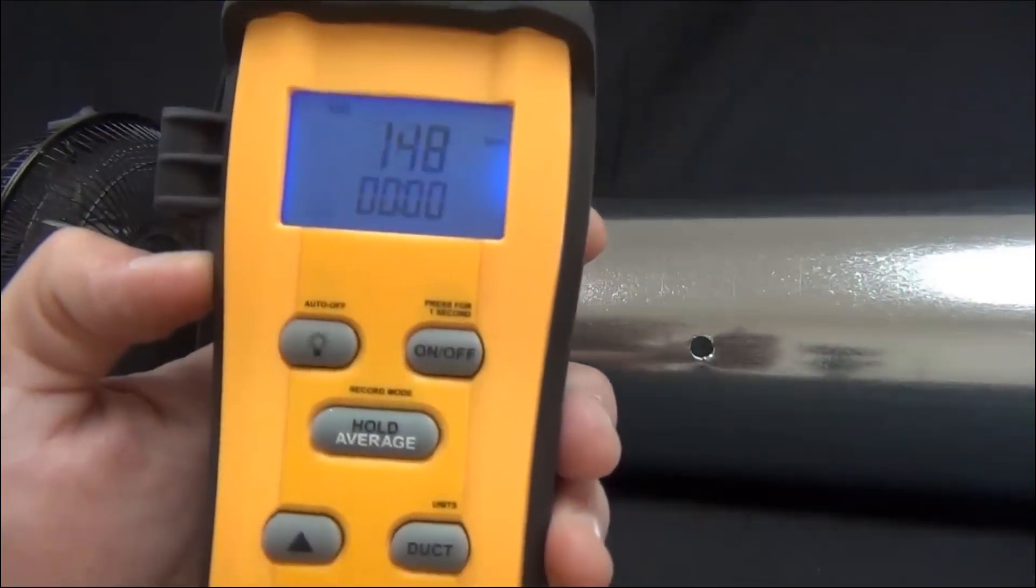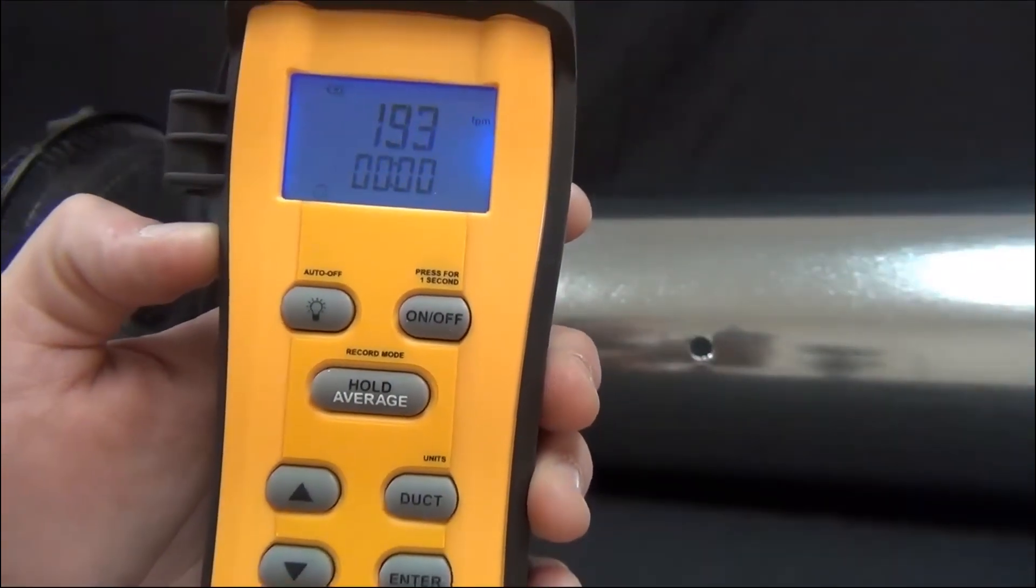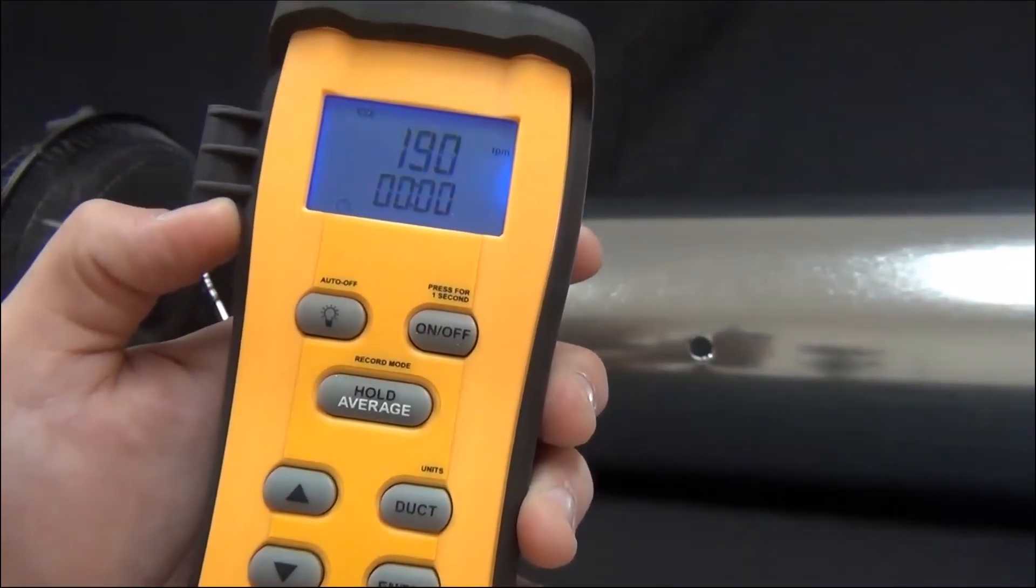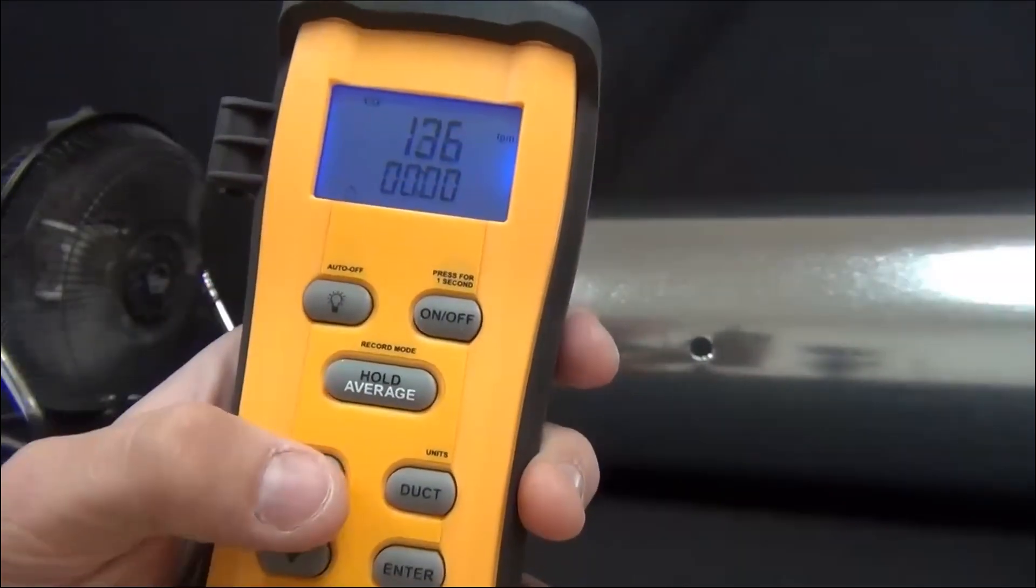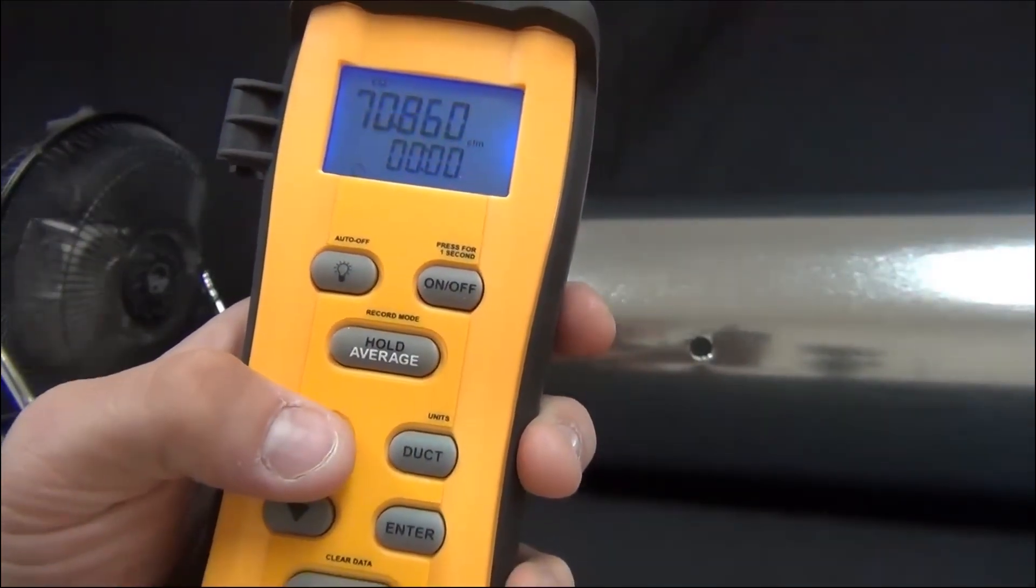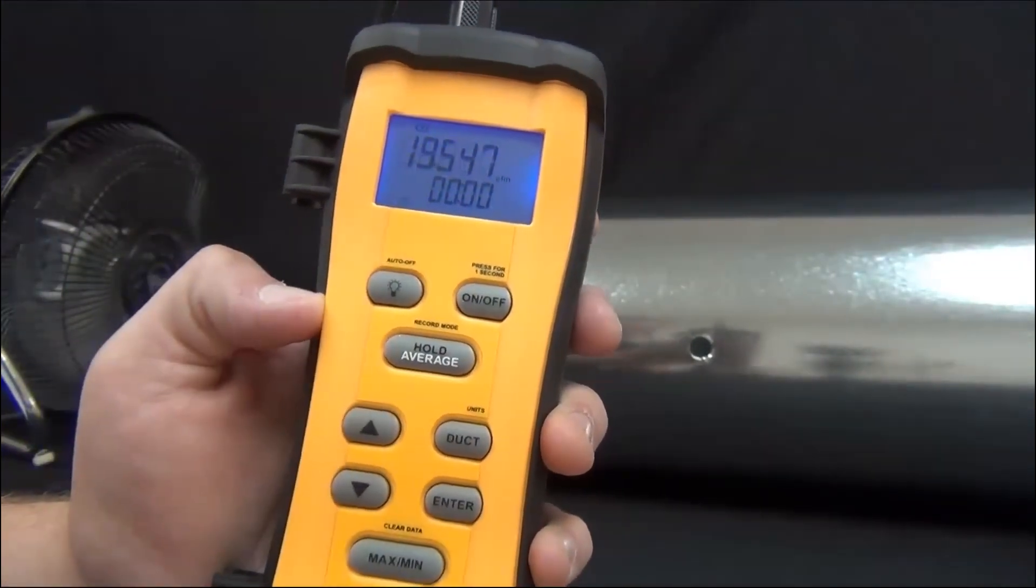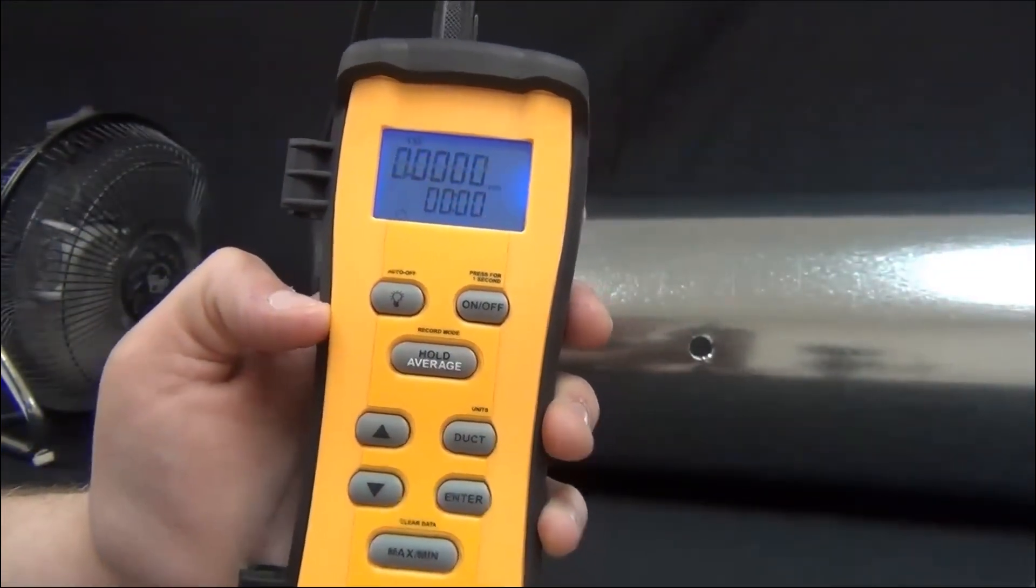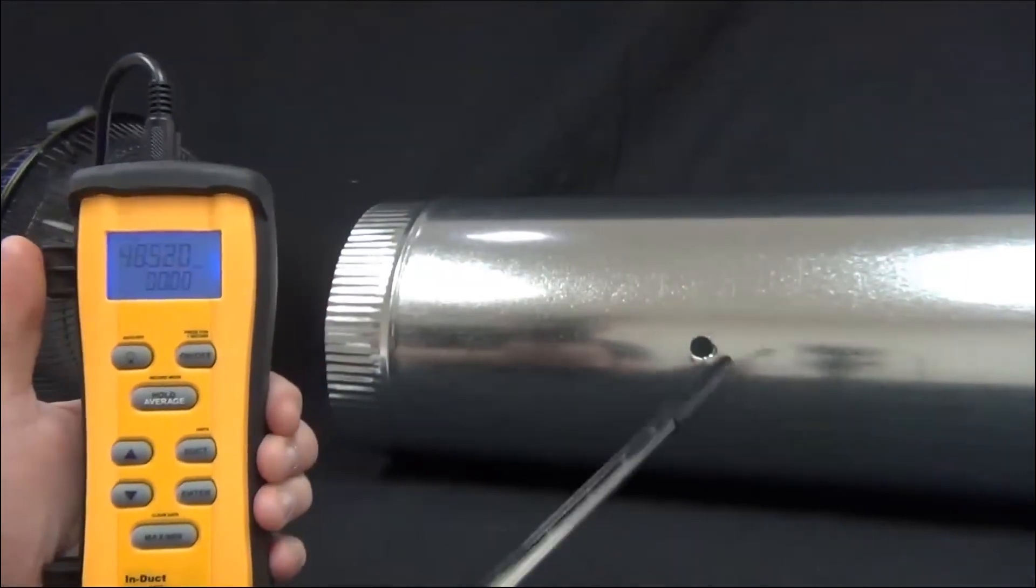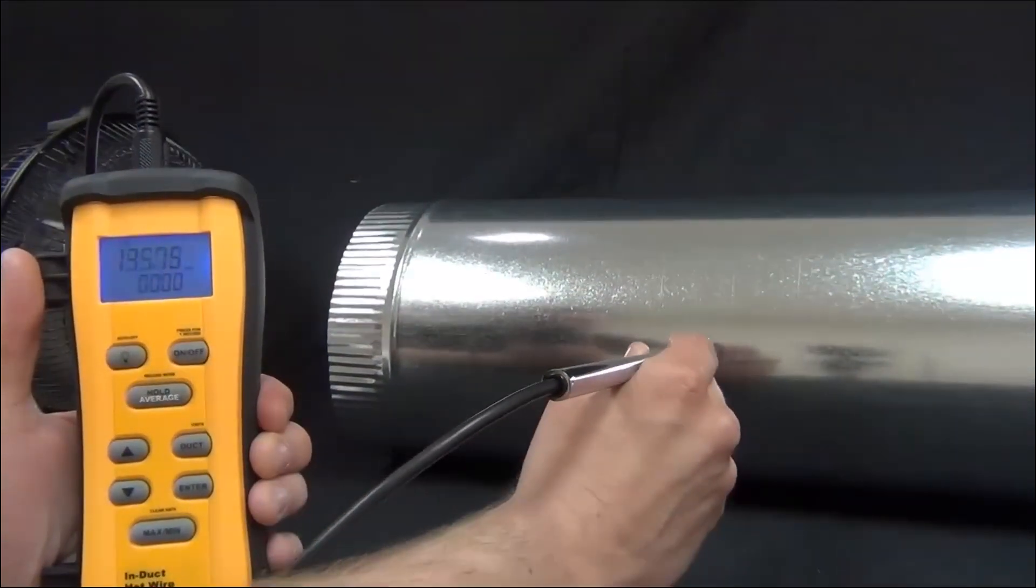And then what you're going to see is the feet per minute as well as the timer to let you know how long you've been taking measurements. You can use the up arrow to switch to temperature or to CFM and watch it as it goes along. So what I'm going to do is leave it on CFM and then stick the wand in the duct. Make sure that the flat side is pointing into the airflow.